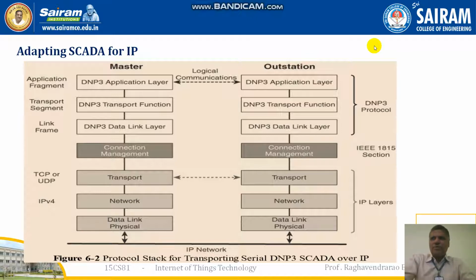DNP3 protocol, that is distributed network protocol, is based on a master-slave relationship. That is, the master is referred to as a powerful computer located in the control center of a utility, and a slave is a remote device with computing resources found in a location such as substations. Now DNP3 refers to slaves as outstations.